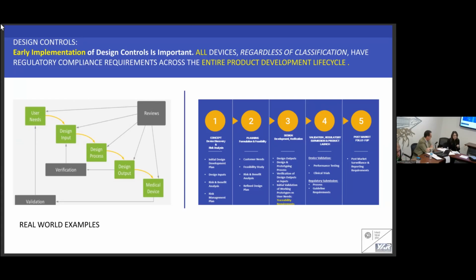And there are 2 key basic pieces of information that I want to impart today specific to that quality management system. Every device, regardless of what classification it is, whether it's a class 1 or a class 2 or class 3, you're obligated to create documentation even early in design as part of the product development process. And where this hurts you is by the time you end up with iteration version 3.0, you've picked up key reasons why you wanted to change it between the first one and the second one and the third one.